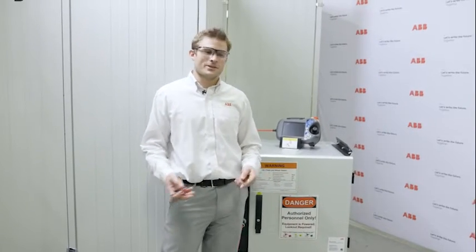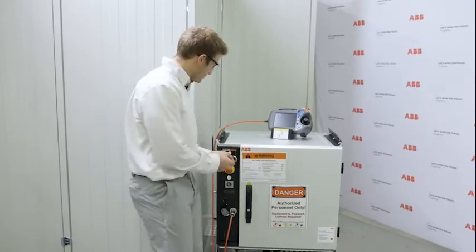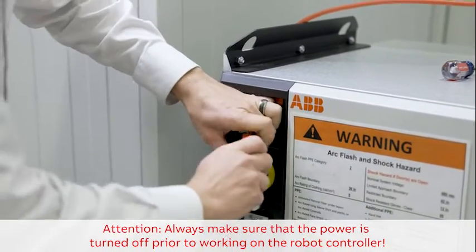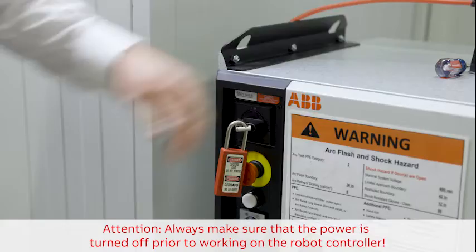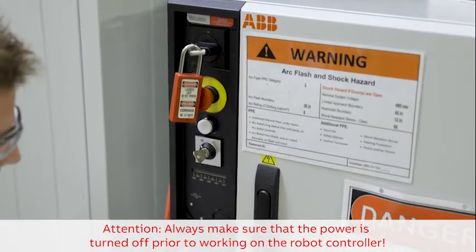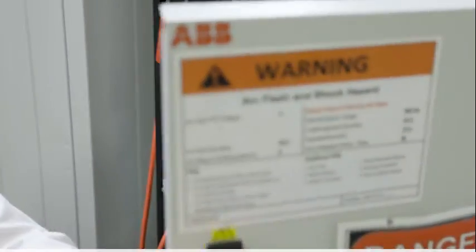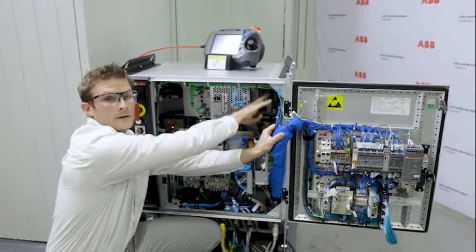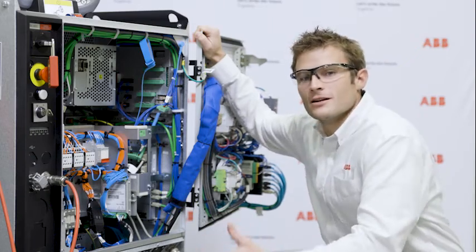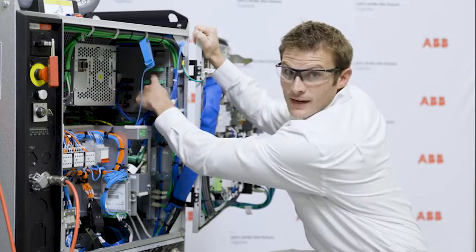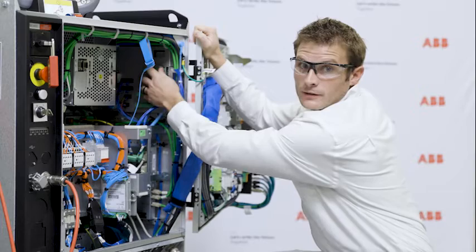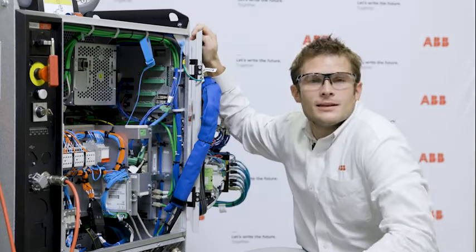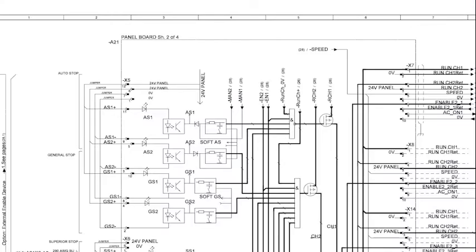Now we are going to show you the physical location within an IRC5 controller of the run chain jumpers. The factory run chain jumpers are located here. The auto stop signals are located on contact connector X5 on the panel board. This panel board currently has the factory jumpers installed. Now let's take a look at the electrical pins.